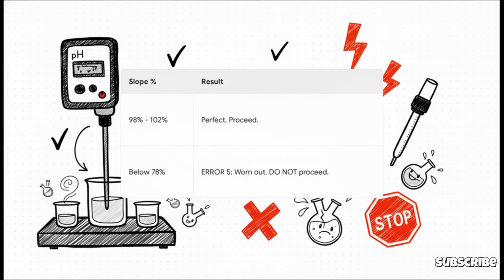Okay, after you calibrate, you get to what I call the moment of truth, the slope check. Think of this as the final exam for your probe. If you get a slope between 98 and 102%, congratulations, your probe passes with flying colors, you're good to go. But if you see a number below 78%, that's a hard fail. This is a big flashing red light, a total stop sign. If you see that error, your probe is screaming at you that it's no longer reliable. If you decide to proceed with your experiment anyway, you're not doing science anymore. You're just making up bad data.